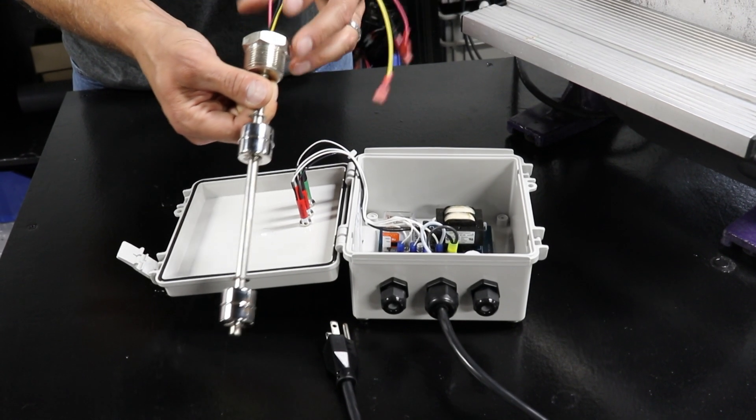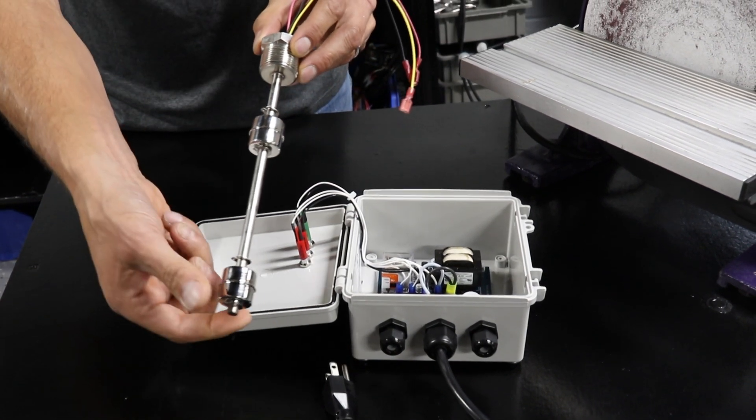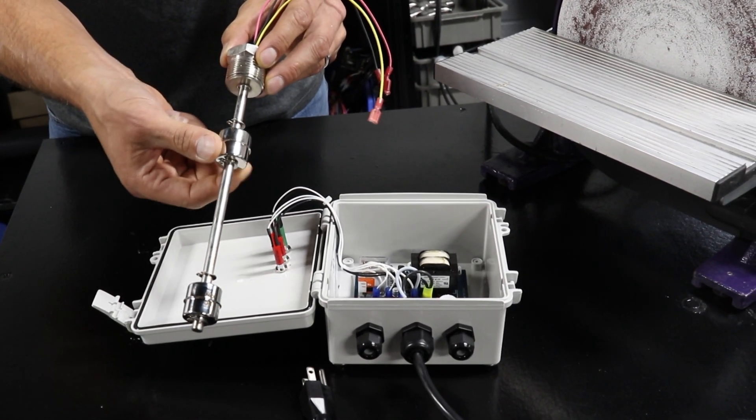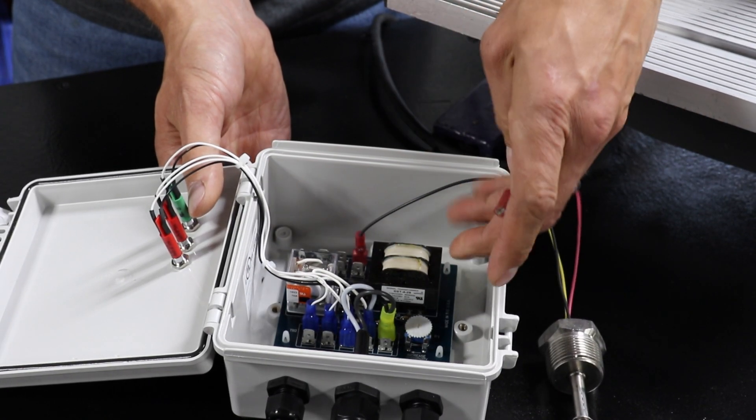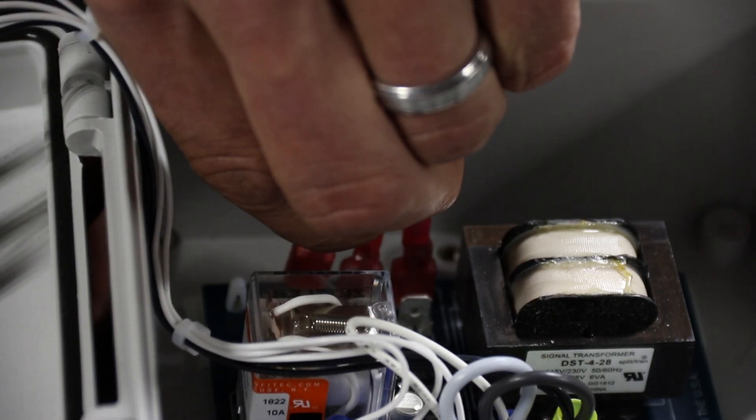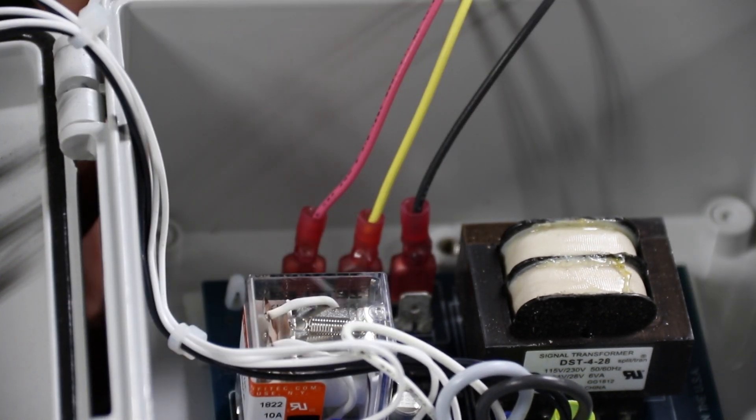What you see here is a basic two level common float switch. It has a low float and a high float and a three wire hookup. The black is the common wire which I'll hook up to this contact on the top row. The red wire is the low and the yellow is the high.